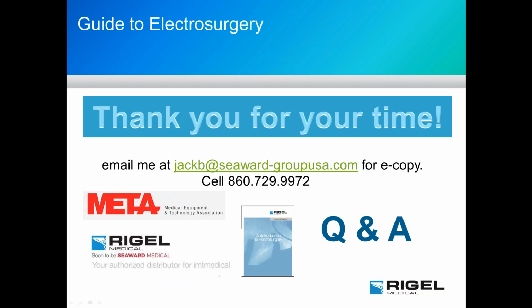So here's a good question. We just replaced our Force FX and Force FXC units. Are the monopolar or bipolar pencils compatible with the FT10 units? As far as test pencils, yes. The LigaSure with the RFID monitor chip in it now has a one-time use. So if you're grabbing something from your surgical inventory and using that as a test pencil, that would be a limitation, but with LigaSure we test via test leads anyway, so that should not be an issue for you.